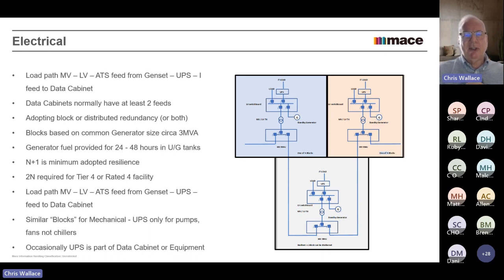Some use this as a little bit of a cheat, because obviously the UPS has some losses. It's normally quite a highly efficient thing, but it has some losses. And if you work out the actual PUE of 1.3 or 1.4, some of that PUE is UPS loss. But if you're supplying a server which has its own built-in UPS, you might be a little bit cheeky and say, well, that is actually only supplying data. But there is actually a tricky bit of UPS loss in the onboard UPS system, if that is the case.